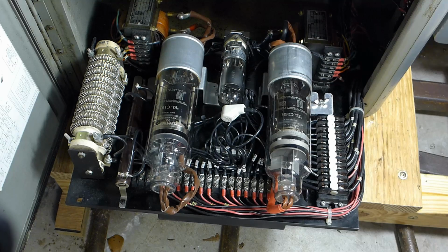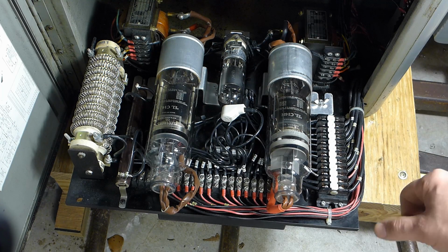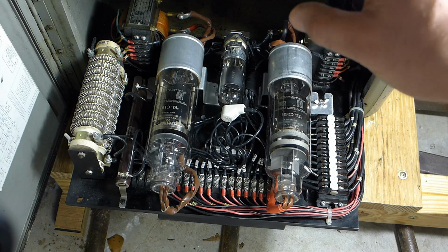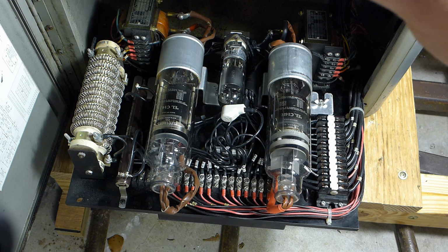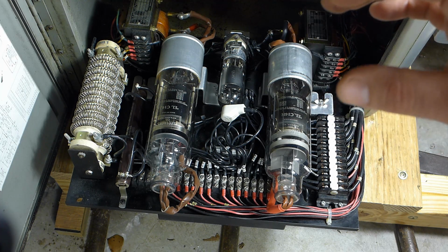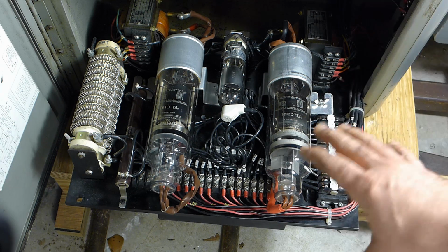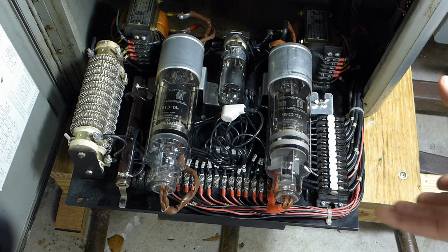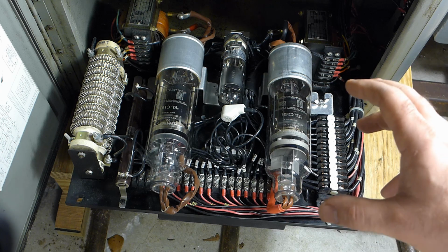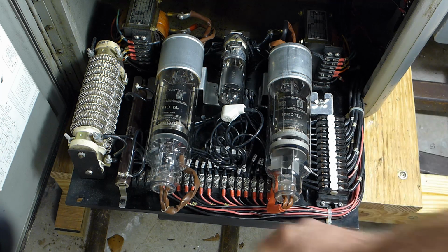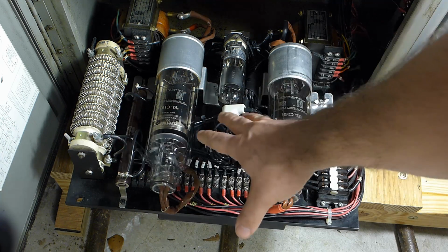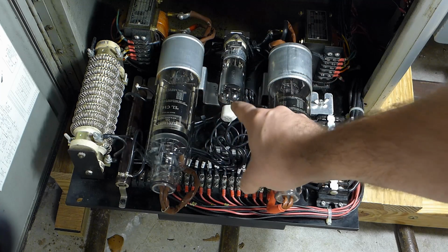This big guy over here is 2 braking resistors. So when you change spindle speed, and the change in speed and the corresponding change in current is great enough, the analog circuitry detects that and knows that you want to change the speed. So if you're wanting to slow down, it will essentially remove power from the motor, short circuit across the motor terminals, and electrically brake it.